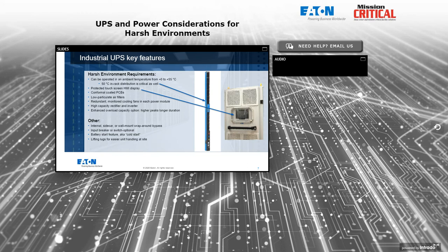And it's more common to see lifting lugs. You see them in yellow in the picture on the right here. Those lifting lugs allow the cabinet to be picked up from the top. Many UPS cabinets today are riveted or bolted construction as opposed to welded frame, and not all of them are amenable to being lifted from the top plate. But it's very common in industrial applications and shipboard applications to require those lifting lugs.